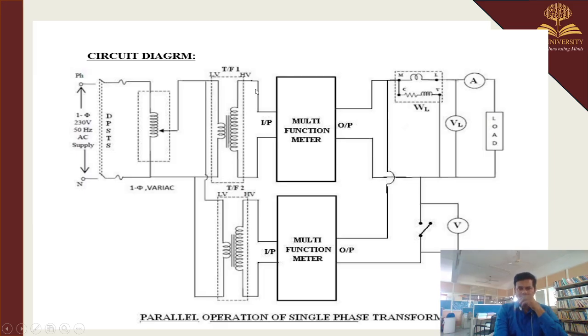On the secondary side, the output of the HV side of TF1 is connected to the input of the multifunction meter. Similarly for the other transformer, we also connect the input to a multifunction meter, which is the output of the secondary terminals of TF2. Then the output of the multifunction meter should be connected to the wattmeter: M and C should be shorted, L is connected to the ammeter, and V is connected in parallel to the load also.